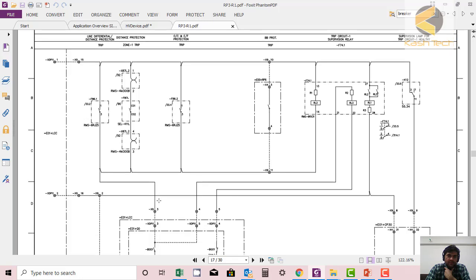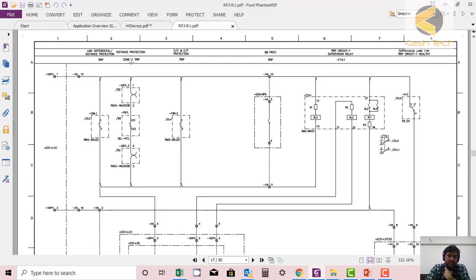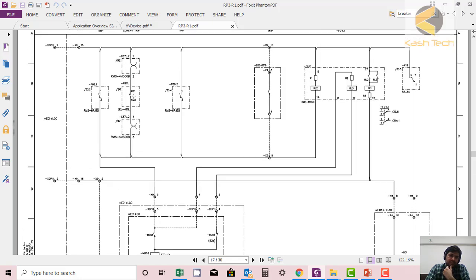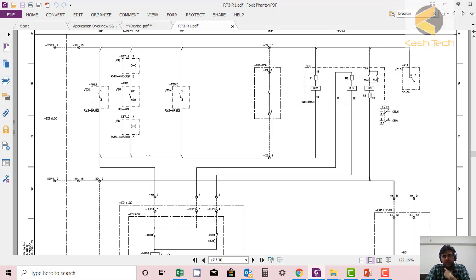Another tripping is from the distance protection relay, tripping in Zone 1. This tripping is direct — not through the lockout relay. The reason is that in Zone 1 most cases require auto-reclosure. If the lockout relay is operated, the breaker is locked and cannot reclose unless someone comes and resets the lockout — electrically or mechanically by hand. That is why direct tripping is provided here. We will understand this in detail in the next phases.